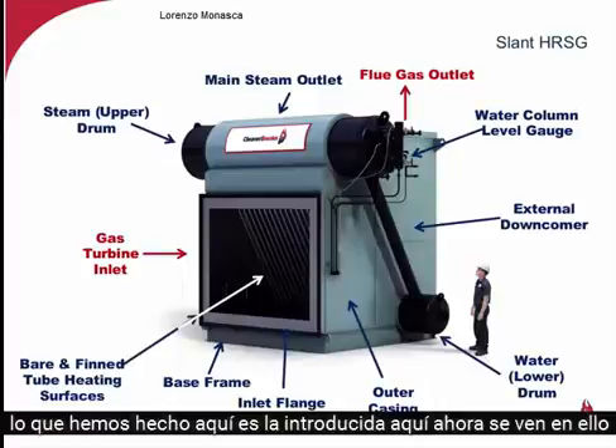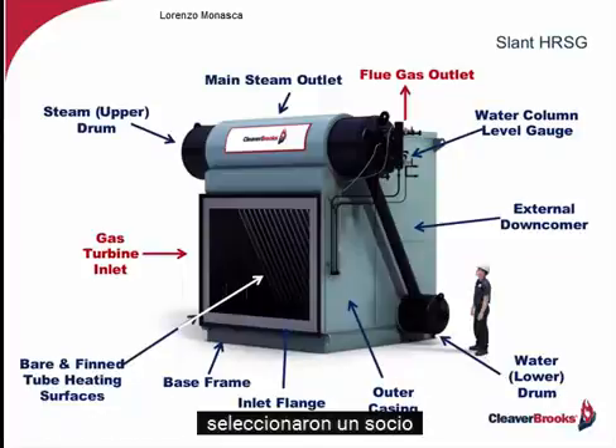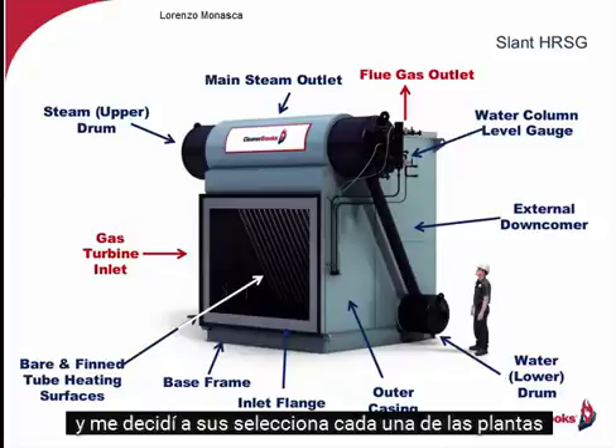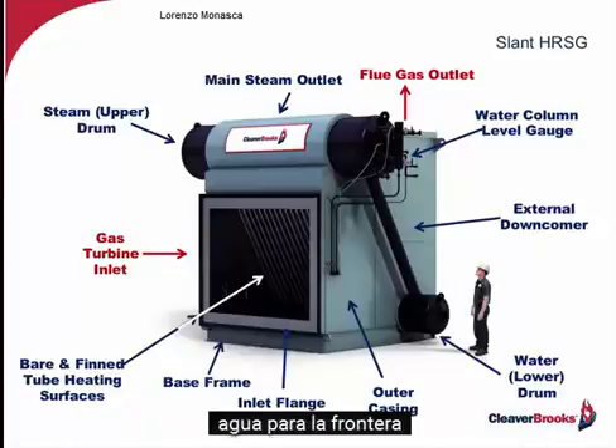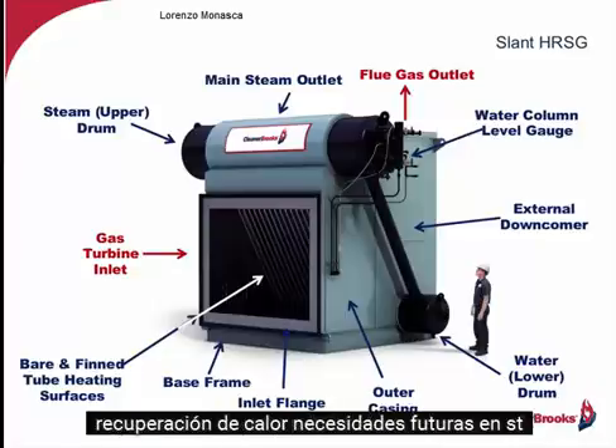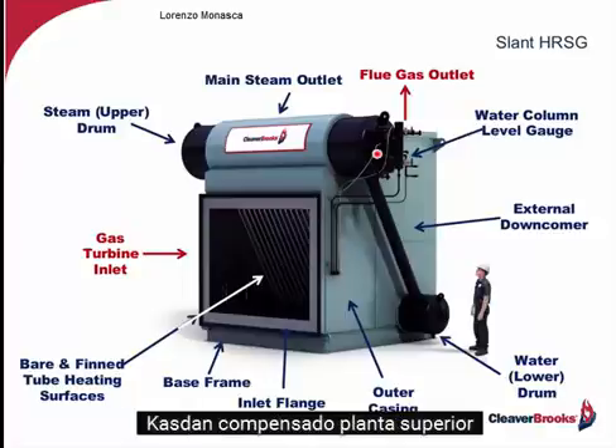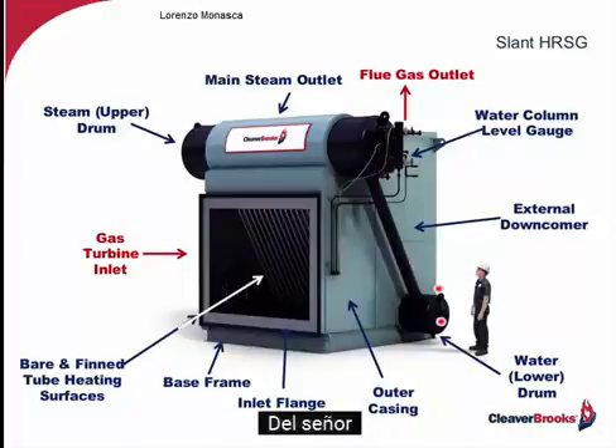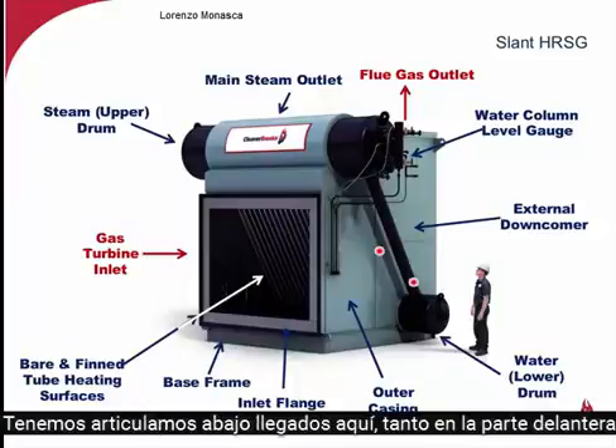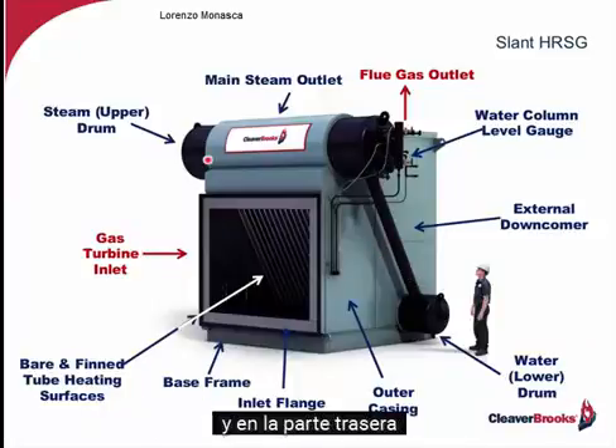What we've done here is the engineer has now looked at it. They've selected a partner, and a design engineer selects a slant water tube boiler for their heat recovery needs, the HRSG. Why? Because, as you can see here, it has an offset upper drum from the lower drum, diagonal. We've got isolated downcomers here, both in the front and in the rear.